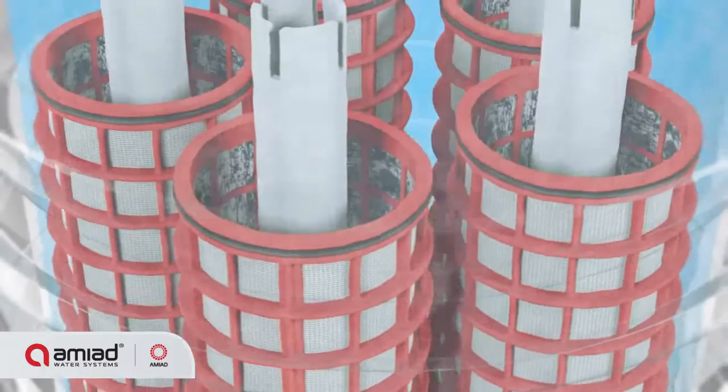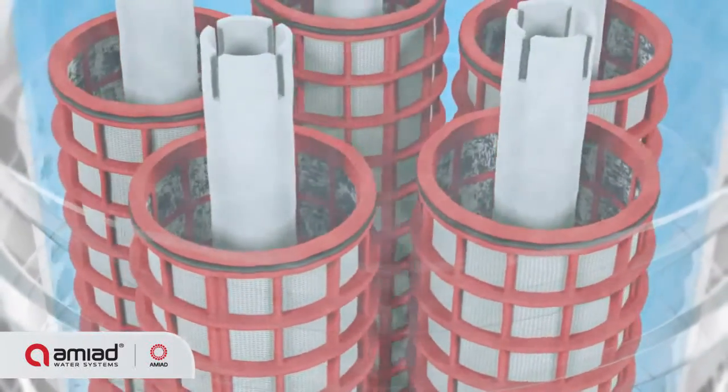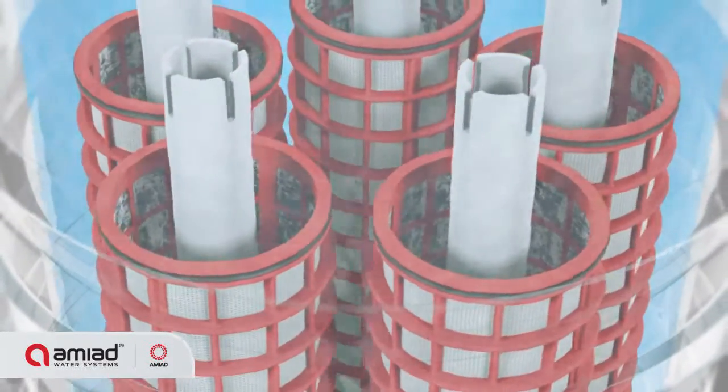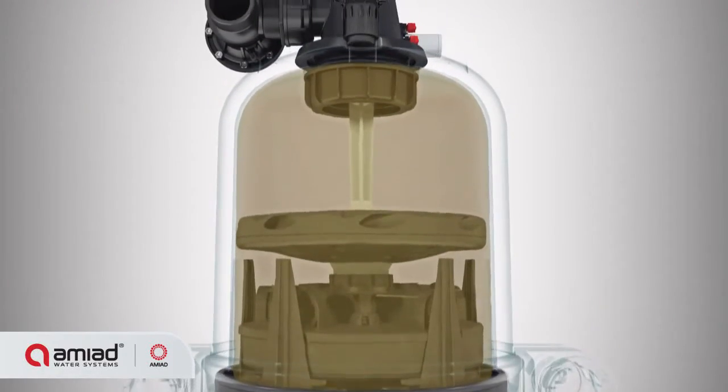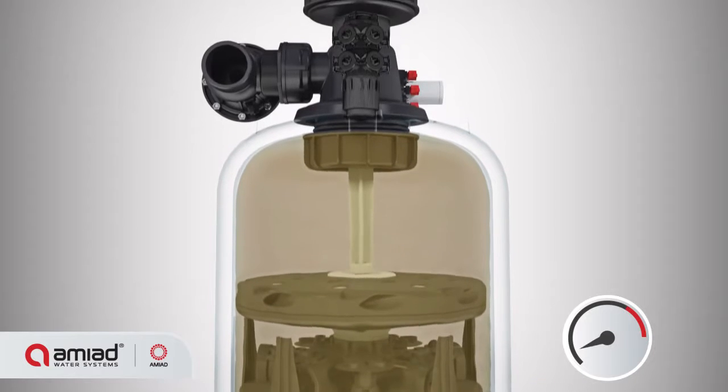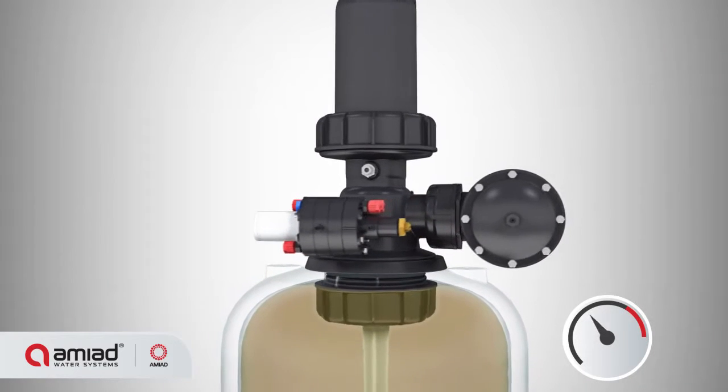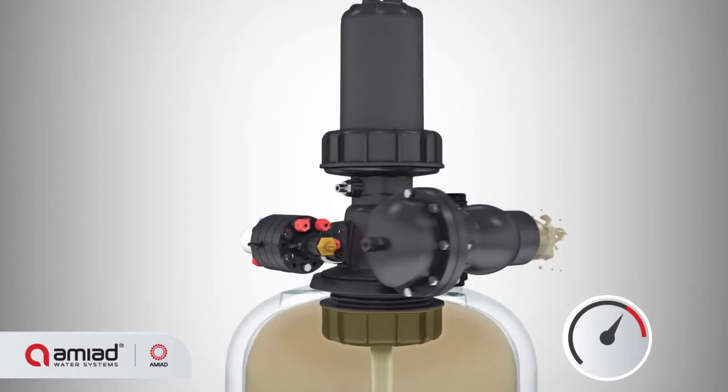The gradual dirt buildup on the screen's inner surface causes a filter cake to develop, with a corresponding increase in the pressure differential across the filter. Once the pressure differential reaches a pre-set level, the system activates its self-cleaning cycle by opening the flushing valve.